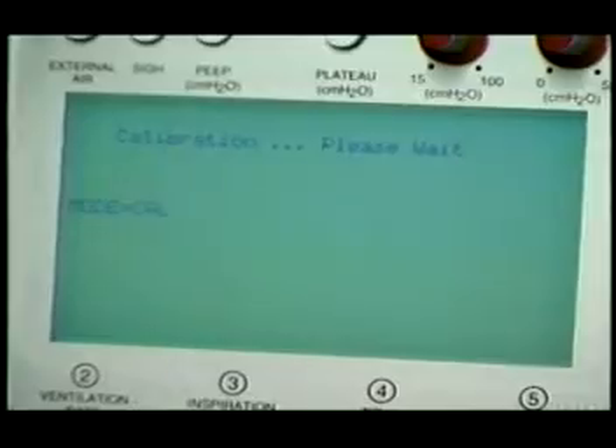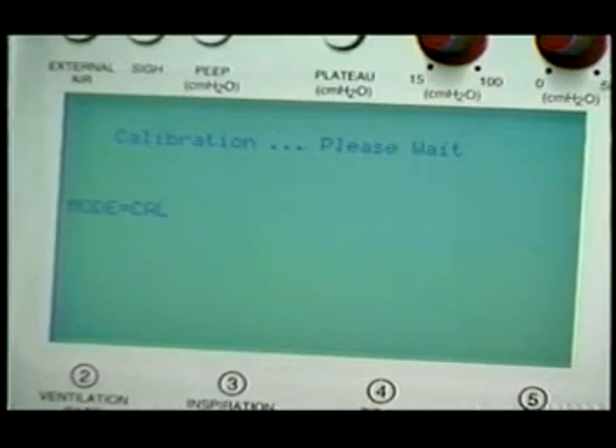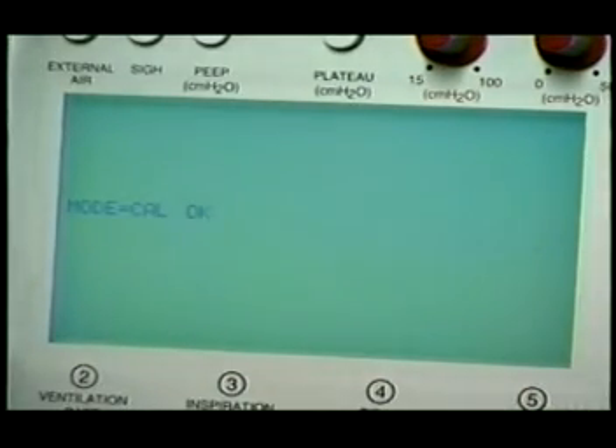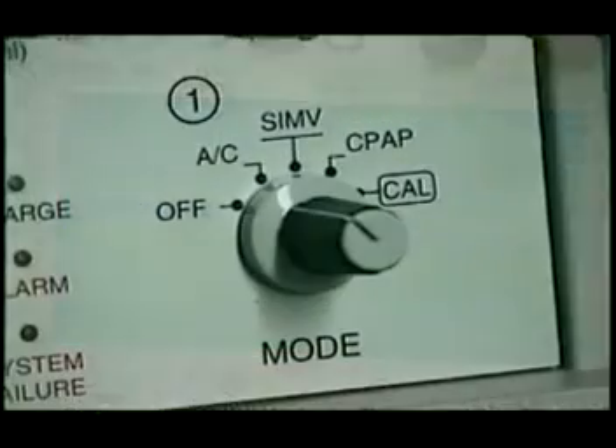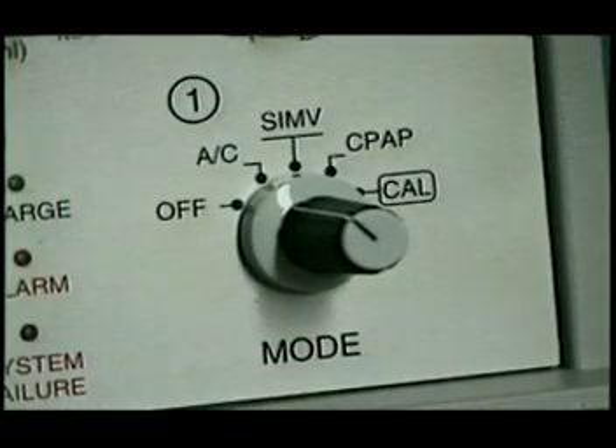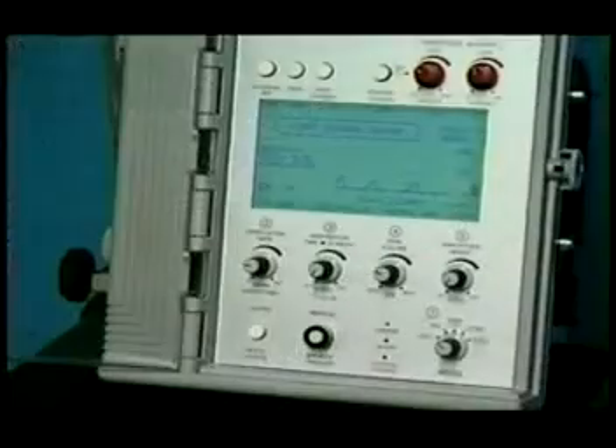To calibrate the internal pressure transducer, turn the mode select switch to the cal position. The LCD display message will tell you to wait. When calibration is finished, the message tells you calibration OK. Turn the mode select switch to any operating mode to begin operation.